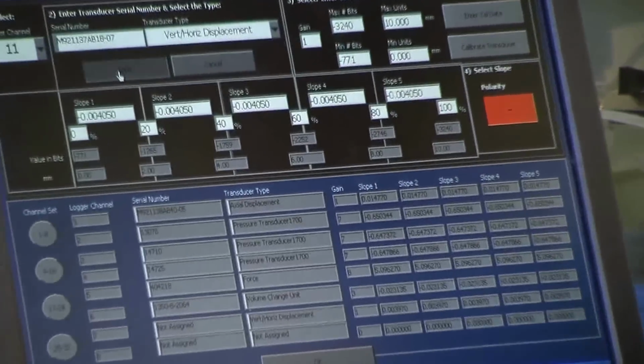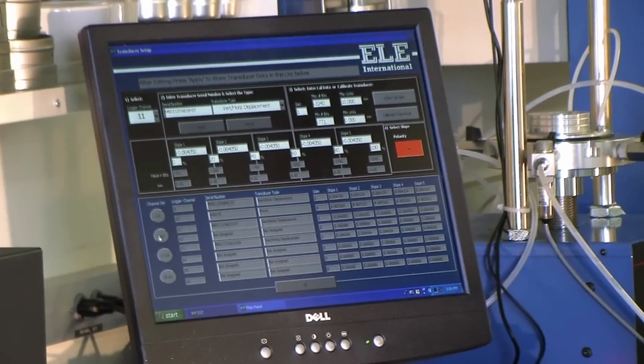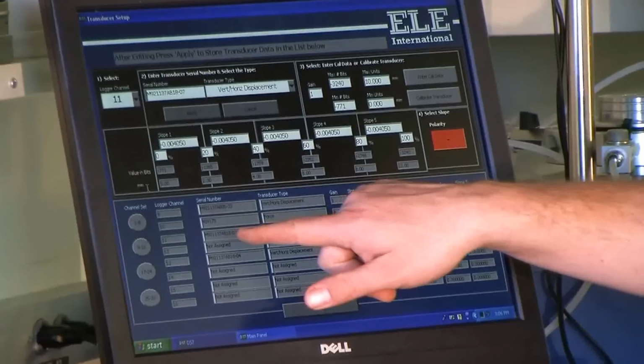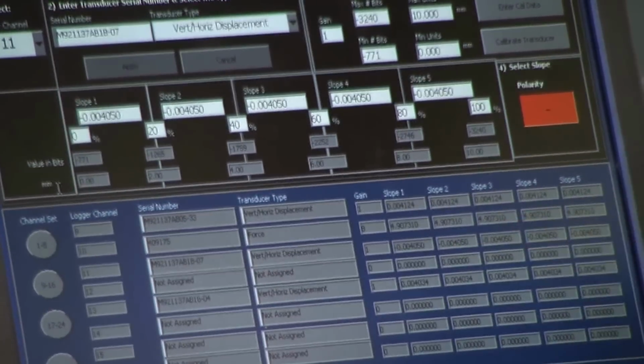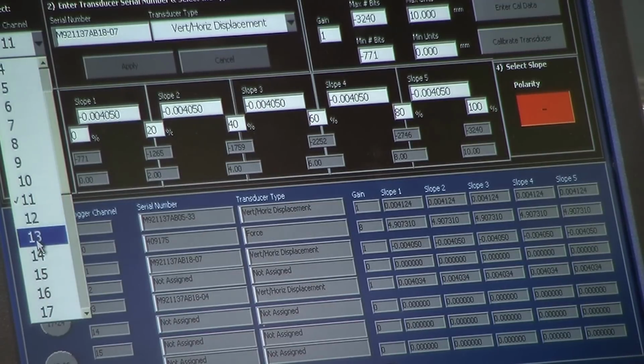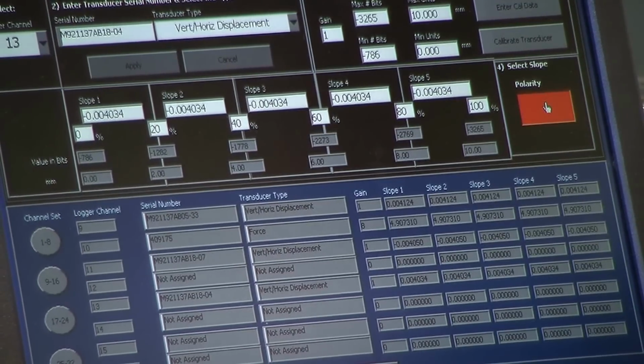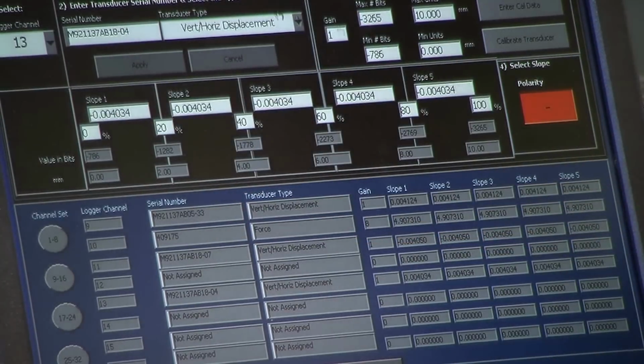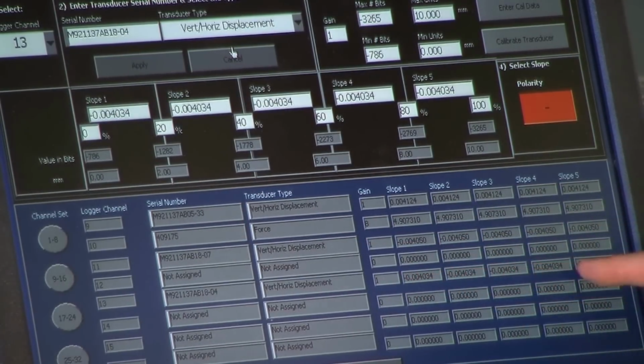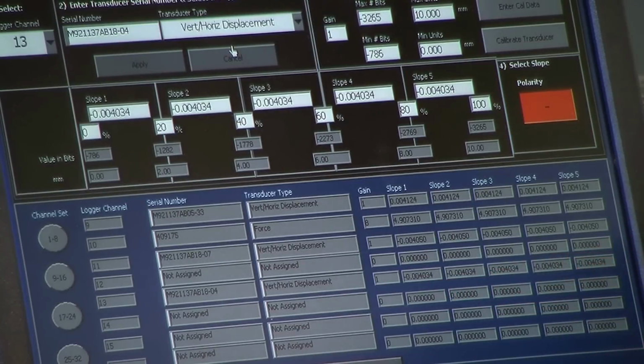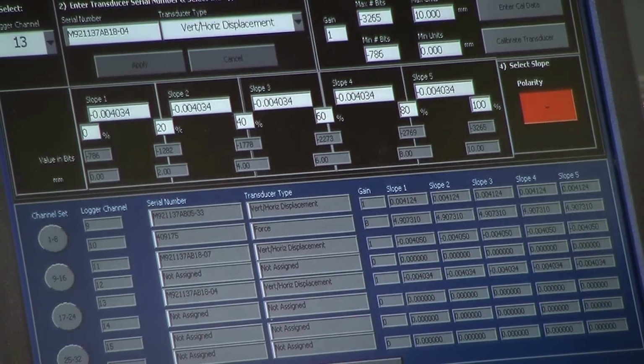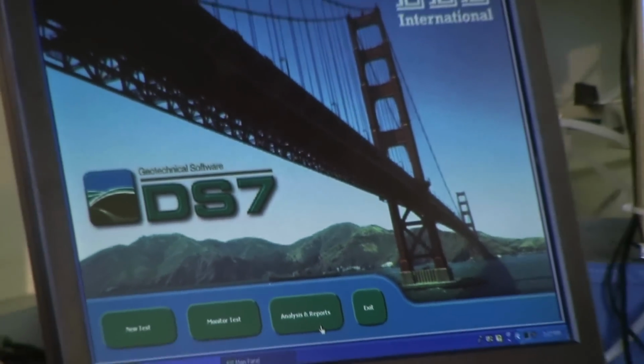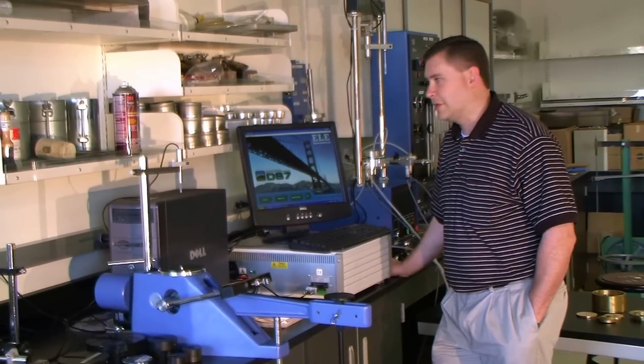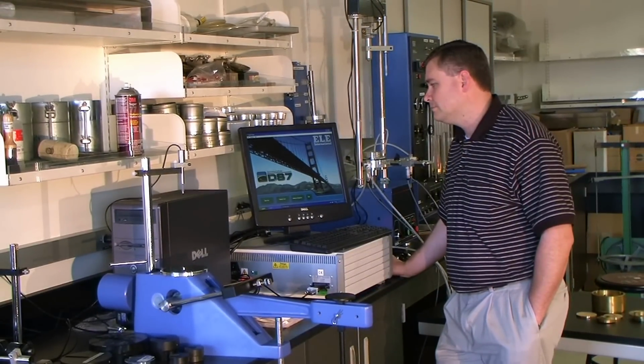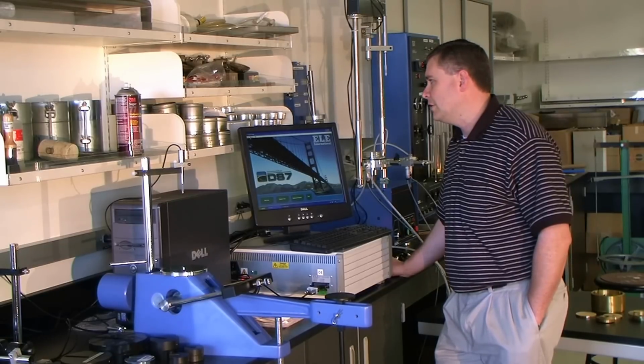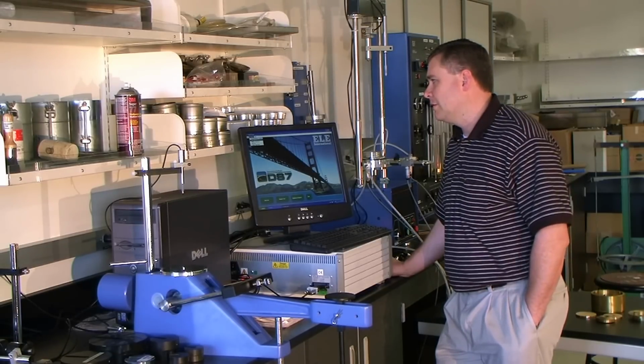Then click the apply button beneath the serial number. And what that does is that if you click on the bottom, the channel set, channel 11 now has negative slopes. We'll do the same for channel 13, which is our consolidation transducer. Click that until you have negative slopes. Then hit apply, and then you'll see the negative slopes have been applied here to the channel set. And then when you click OK, that data will be saved to the calibration files that are on the computer. Okay? So now we've verified that our transducers are reading appropriately.